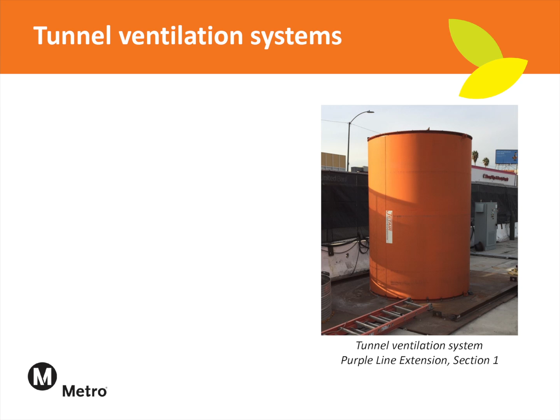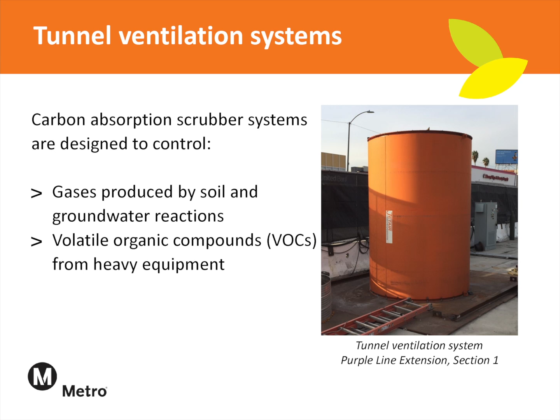For example, tunnel ventilation systems are designed to remove harmful gases from the tunnel operations. On the Purple Line Extension Section 1, contractors recognize that tunnel operations can release gases, such as hydrogen sulfide, produced by the reaction between soil and groundwater, and volatile organic compounds, or VOCs, can be produced by heavy equipment operating underground. The carbon absorption scrubber system installed on the tunnel ventilation system was designed to treat the air and remove such contaminants before they could be released into the community.